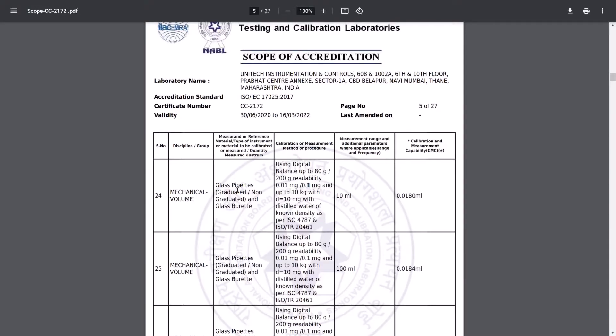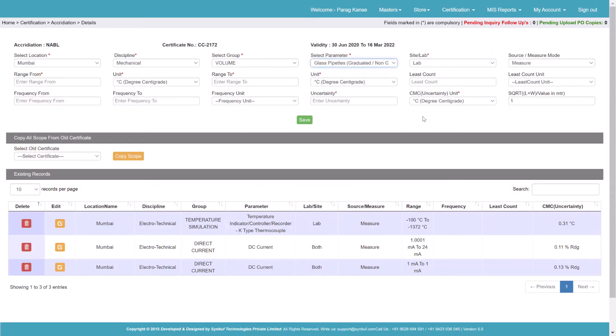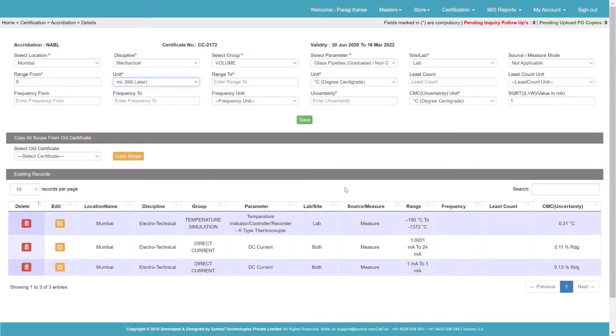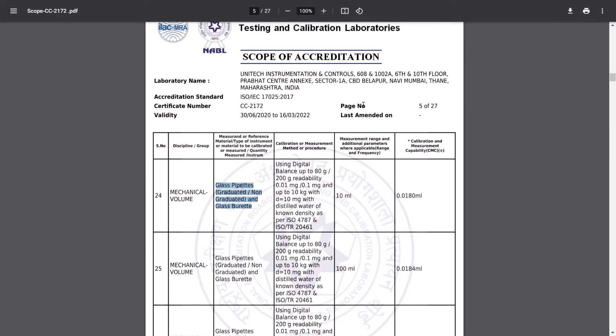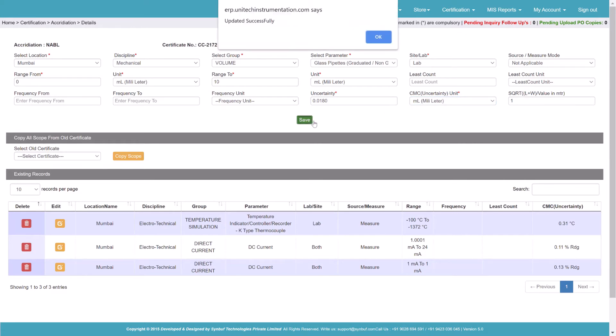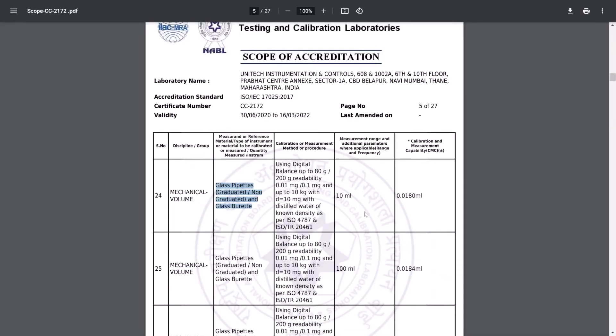This is the given parameter in the accreditation body. This is a facility for lab — I'll select accordingly. This is source/measure — not applicable in this case, so I will select Not Applicable. The range is 10 ml, so I will enter 0 ml to 10 ml. My uncertainty is 0.018 ml — 0.0180 ml. This is my way to update this case.